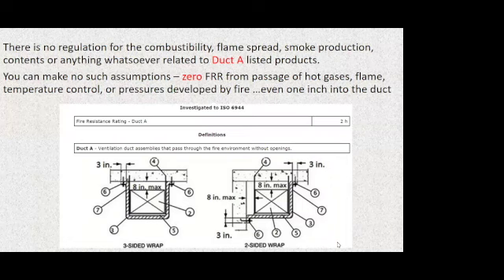And unfortunately, that duct A seems innocuous over there because it says fire rated, it says 2 hours. That's what I want. I need the U shape or I need the L shape. That's what I want. But if you don't know that, at the top of the page in that very first line, the very first row, you should be having red alarm bells go off in your head when you see duct A without duct B, because it tells you that this product configuration was only provisionally tested.